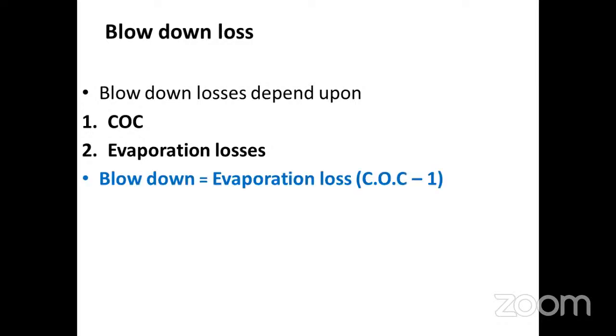Blow down losses depend upon COC and the evaporation loss. When COC increases, we have to blow down. Evaporation losses, we have to make up. Blow down is equal to evaporation loss divided by COC minus one. Blow down process is letting out some amount of water. Yes, sir, we are doing it.